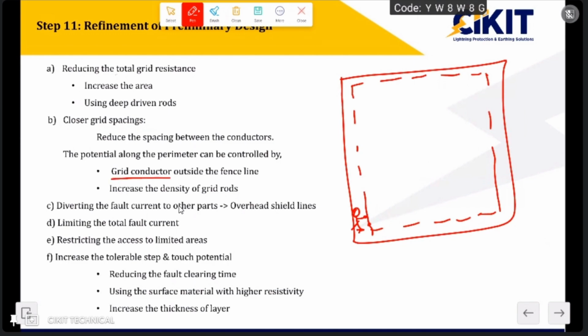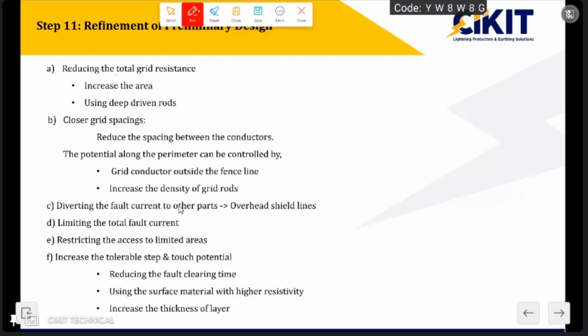And the second one is increasing the density of ground rods. If I increase the density of ground rods on the perimeter, the voltage can be maintained at lower values. So by increasing the density of ground rods along the perimeter, we can maintain the voltage at the perimeter at a lower value. And another option will be providing closer spacings near this perimeter.